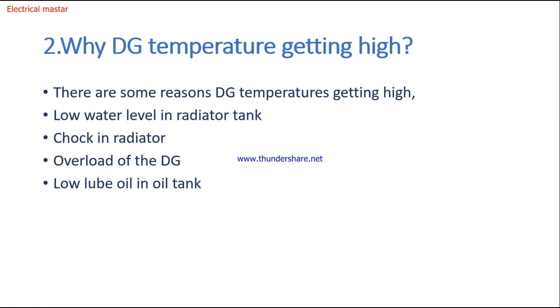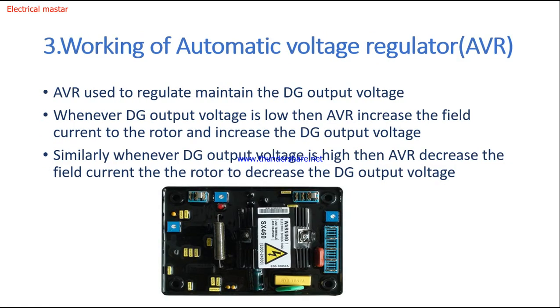The second question: why does the diesel generator temperature get high? There are some reasons. First, low water level in the radiator tank — the radiator tank cools the engine, so low water will cause high temperature. Second, a choked radiator. Third, overload of the DG. Fourth, low lube oil level in the oil tank. These four conditions will make the diesel generator temperature high.